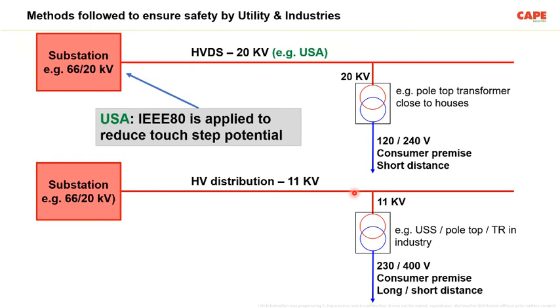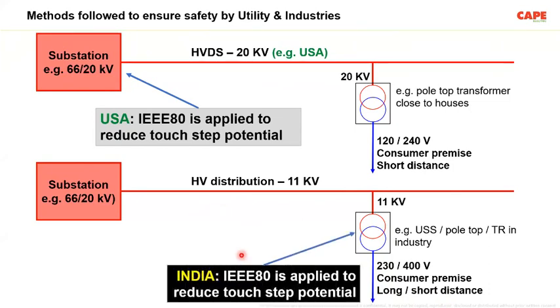We have a distribution of 11 kV and our transformers are comparatively larger in size. It is not 10 kVA or 20 kVA, but these are larger transformers, and one transformer is probably supplying several consumers, for example, 100 houses, 200 houses, and that much. And the line length is long for public distribution and short for industrial distribution. Now, under this circumstance, the biggest mistake is we are trying to make an earth grid for this transformer as per IEEE 80. We want to make an earth grid, gravel resistivity test, touch voltage, step voltage test, or all the safety measures as per IEEE 80.